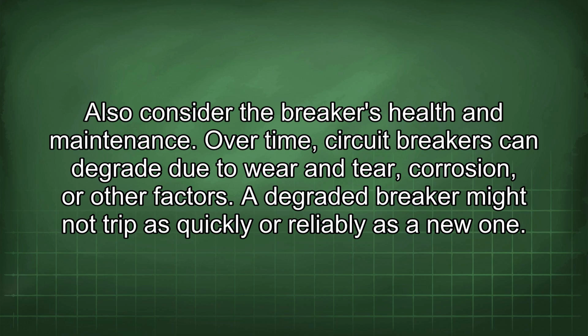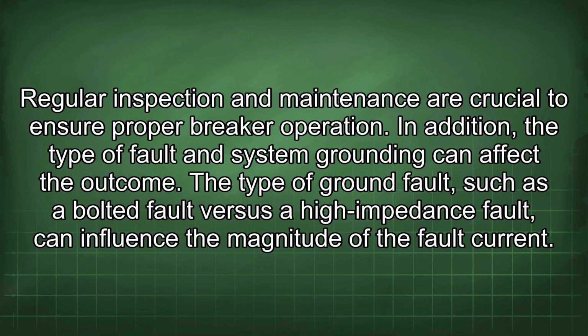Over time, circuit breakers can degrade due to wear and tear, corrosion, or other factors. A degraded breaker might not trip as quickly or reliably as a new one. Regular inspection and maintenance are crucial to ensure proper breaker operation. In addition, the type of fault and system grounding can affect the outcome.